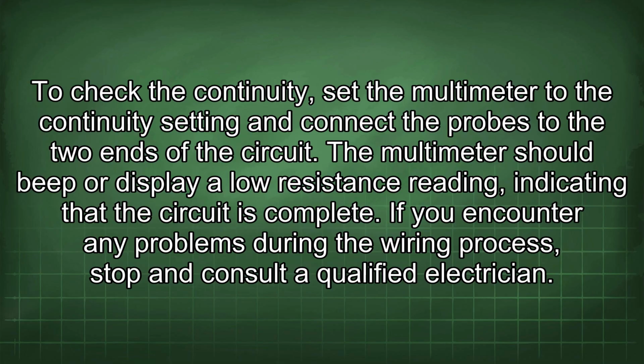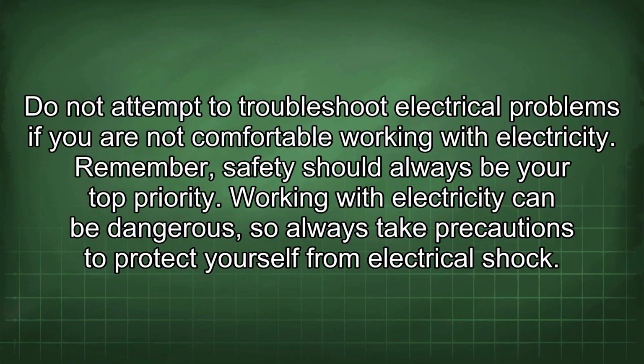To check the continuity, set the multimeter to the continuity setting and connect the probes to the two ends of the circuit. The multimeter should beep or display a low resistance reading, indicating that the circuit is complete. If you encounter any problems during the wiring process, stop and consult a qualified electrician. Do not attempt to troubleshoot electrical problems if you are not comfortable working with electricity. Remember, safety should always be your top priority.